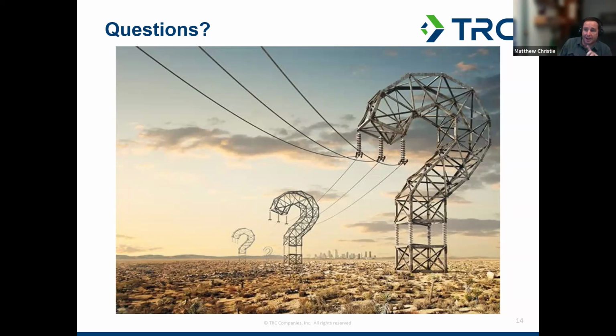Where you're gonna have high draw with a heat pump is if you've partnered it with an electric resistance backup heater, right? And that'll be existing in ducted heat pumps quite often. And they'll put that in for 2 reasons. One is emergency backup if your compressor fails. And 2 is during defrost cycles. Heat pumps need to defrost the coils once every couple hours.